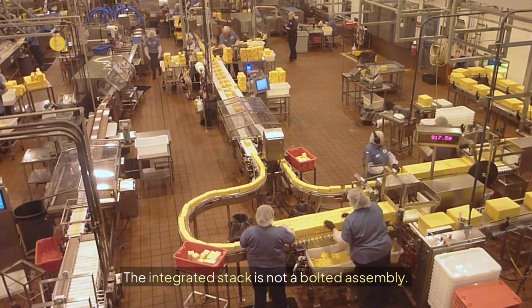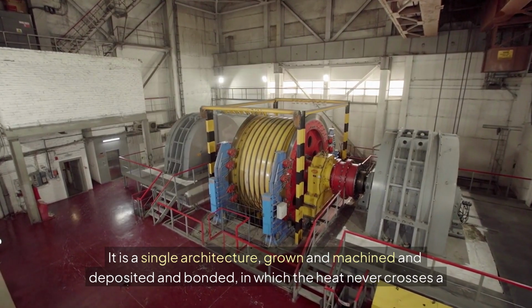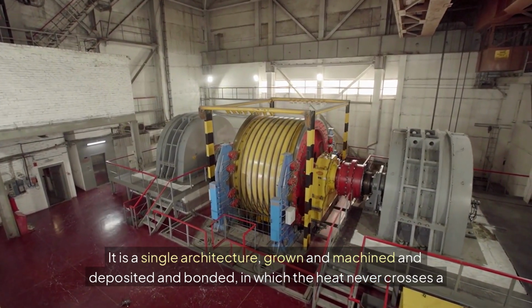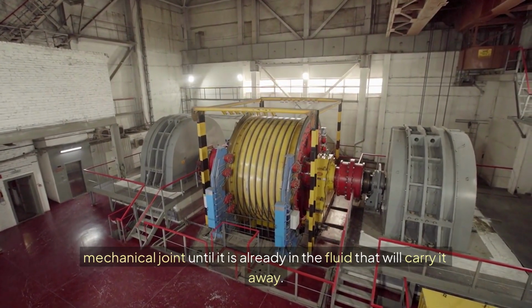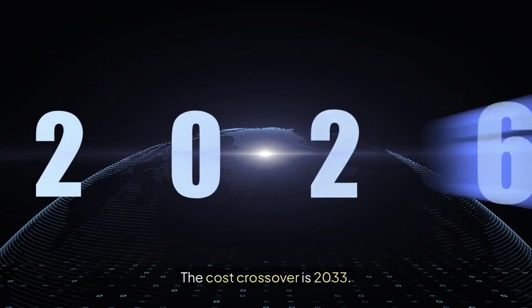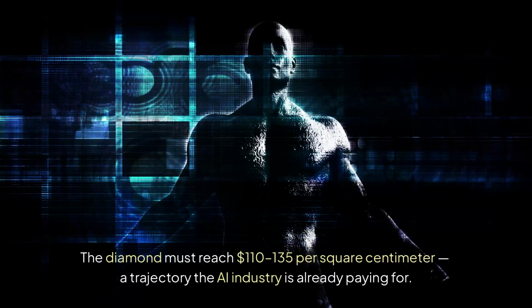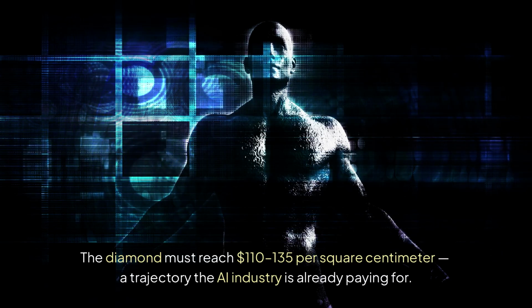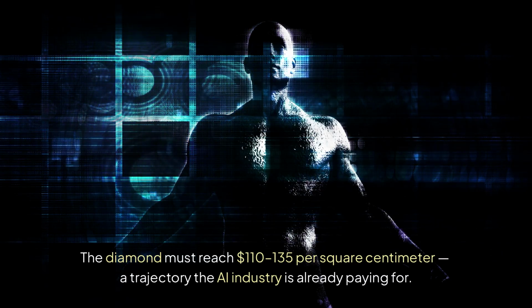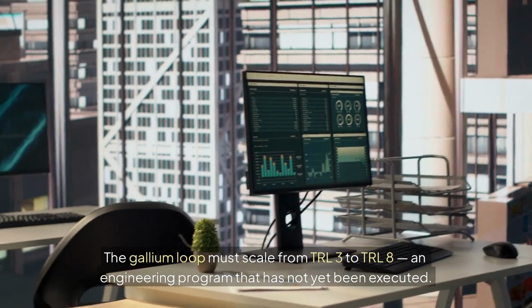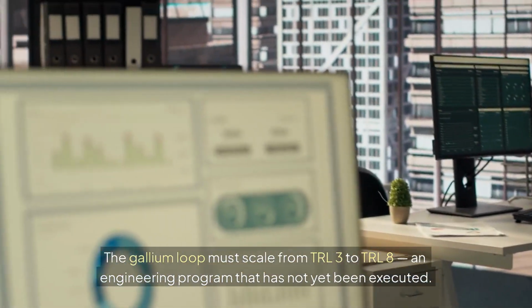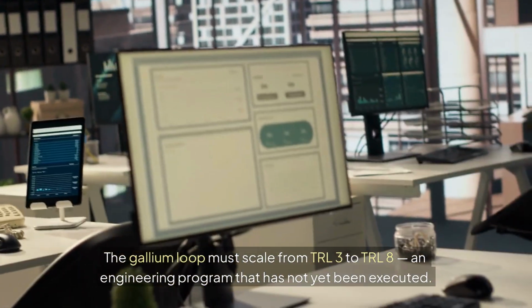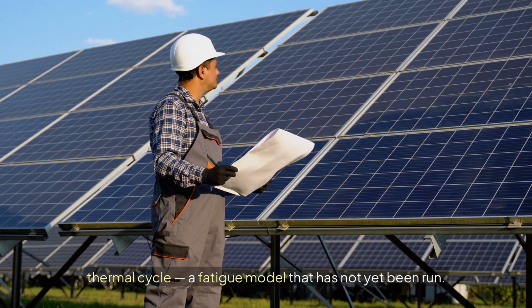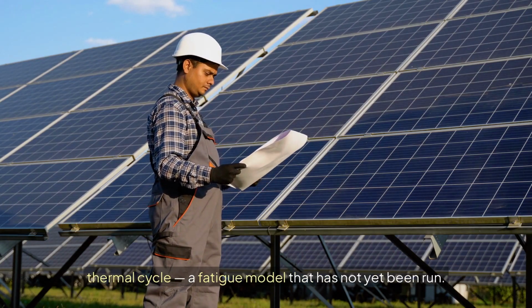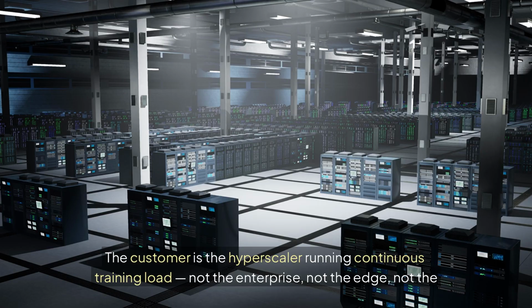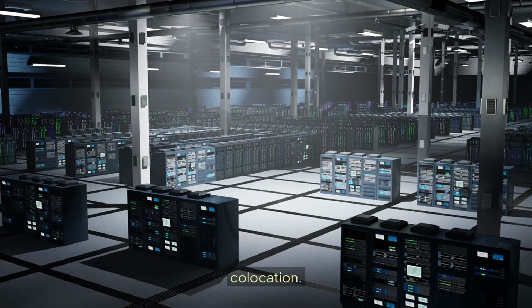The integrated stack is not a bolted assembly. It is a single architecture, grown and machined and deposited and bonded, in which the heat never crosses a mechanical joint until it is already in the fluid that will carry it away. The cost crossover is 2033. The diamond must reach $135 per square centimeter, a trajectory the AI industry is already paying for. The gallium loop must scale from TRL3 to TRL8, an engineering program that has not yet been executed. The tantalum barrier must be validated for the data center thermal cycle, a fatigue model that has not yet been run. The customer is the hyperscaler running continuous training load, not the enterprise, not the edge, not the colocation.